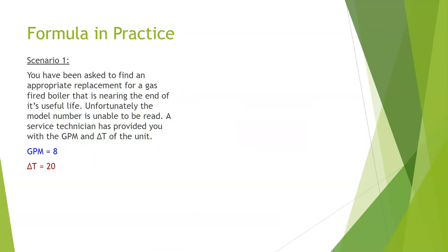Let's put our formula into practice. Scenario one: you have been asked to find an appropriate replacement for a gas-fired boiler nearing the end of its useful life. Unfortunately the model number is unable to be read. A service technician has provided you with the GPM and delta T of the unit. GPM equals 8, delta T equals 20. The first thing we need to do is use our equation: BTU equals GPM times delta T times 500. I can't stress enough, whenever you're using this calculation, write it down on your scratch paper. It's a very simple equation but it only takes one mistake to throw the whole thing off.